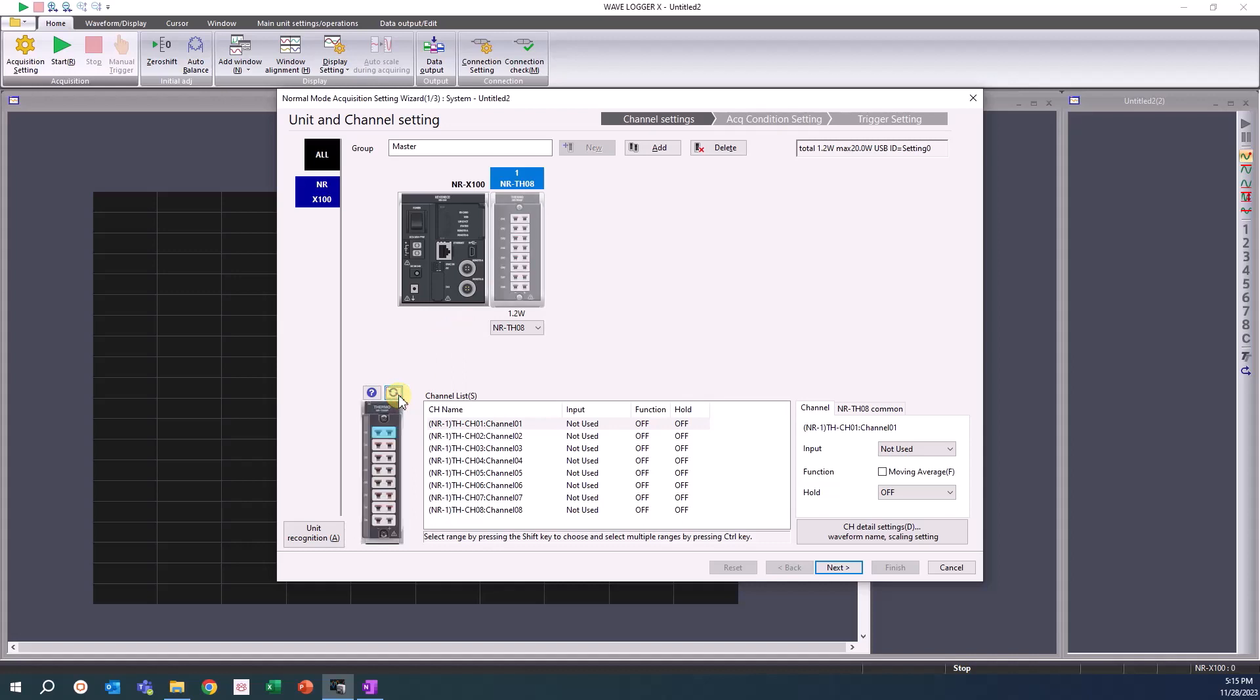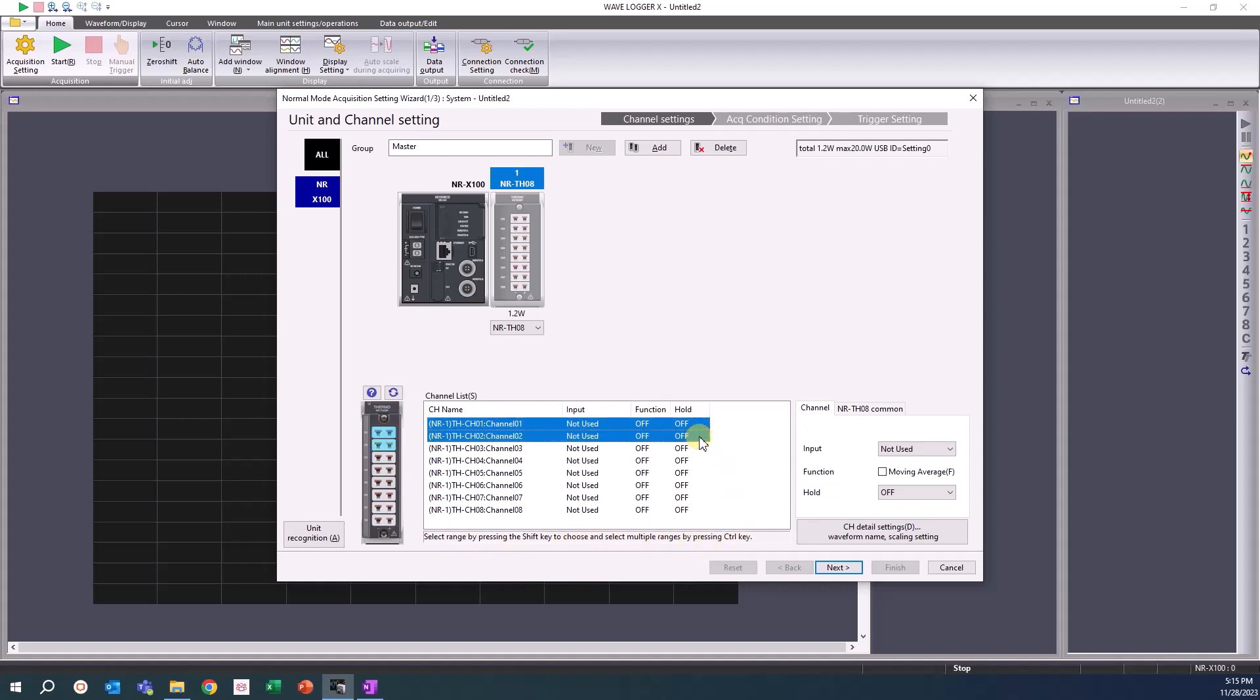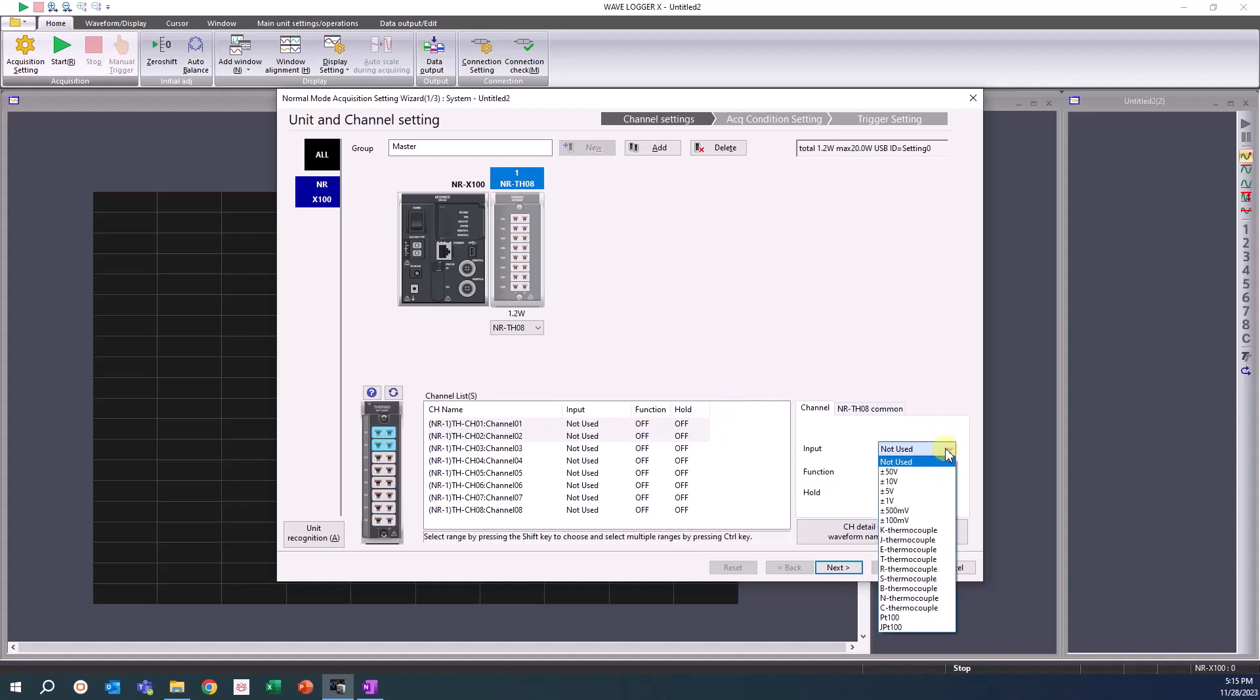To assign an input channel, simply click on the measurement unit and select the desired channel or channels from the channel list. As with other PC software, by shift-clicking the two channels, both can be selected and their input settings can be set simultaneously. In this example, there are two K-type thermocouples connected to input channels 1 and 2.